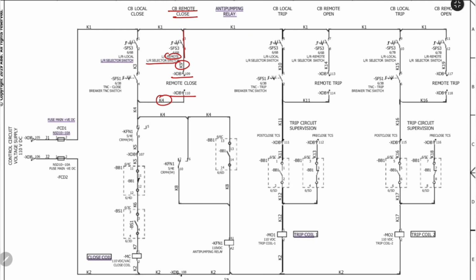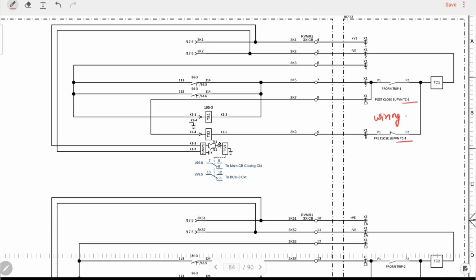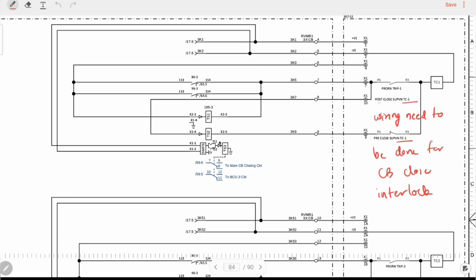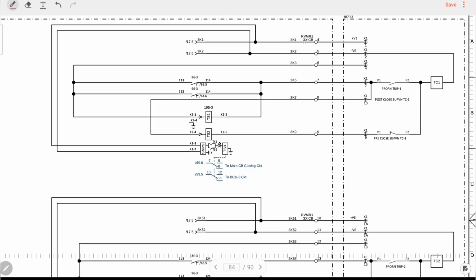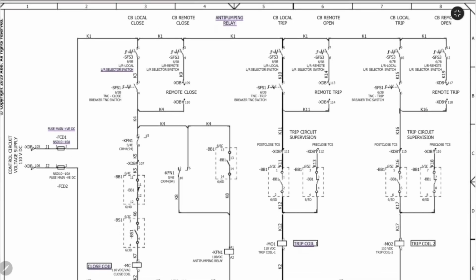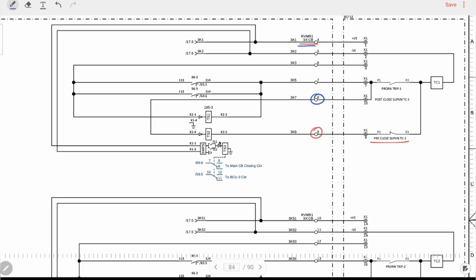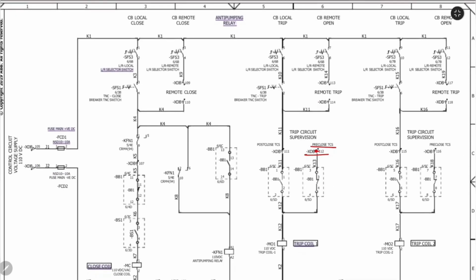Quick tech tip, if you try remote closing at this stage, it probably won't work. That's because the Siemens panel still expects the trip circuit supervision loop to be healthy. Let's wire that next. Trip circuit supervision ensures that the trip circuit remains healthy whether the breaker is open or closed. Connect Siemens terminal 3xCB9, which is the pre-close supervision point, to breaker terminal XDB112. Connect Siemens terminal 3xCB8, the post-close supervision point, to breaker terminal XDB111.